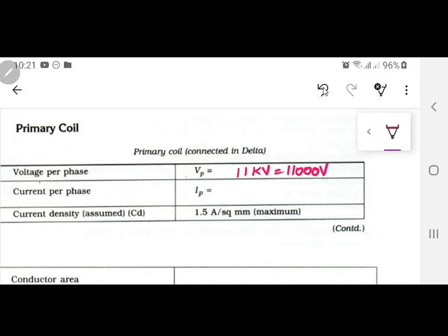How will we calculate it? You have a 100 kVA transformer. So you are going to divide 100 kVA by, since we are talking about the phase current, not under root 3 but 3, and then 11. Give me the answer please on this one. 3.03.